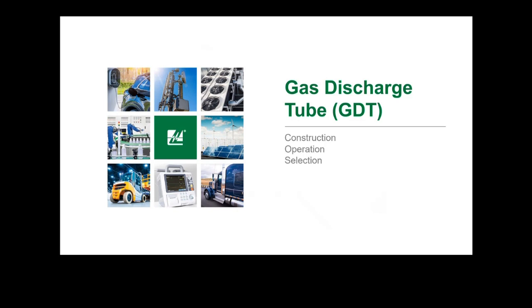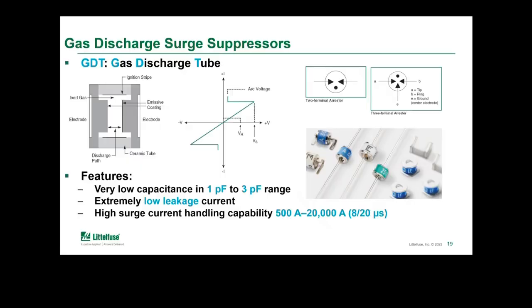So the next device I'm going to talk about is a gas discharge tube. A gas discharge or plasma device acts like a voltage-dependent switch. It's a hermetically sealed chamber that contains an inert gas with some outer and inner electrodes, and these can be either 2-terminal or 3-terminal devices. How they operate is, once the voltage exceeds a certain breakdown voltage, it ionizes the gas internal to the chamber and creates an arc that jumps across the inner electrodes. And this causes the voltage to drop to somewhere around a 10 to 35 volt range.